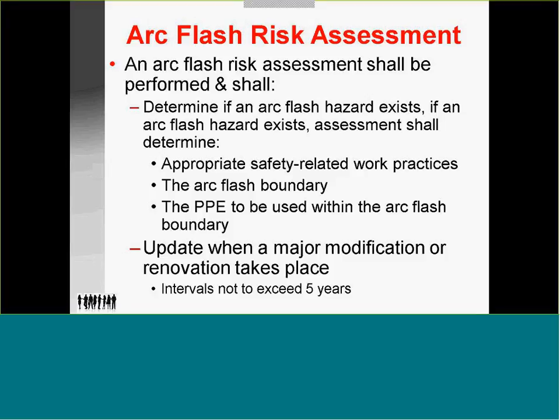Appropriate safety-related work practices, shielding, barriers, anything to protect the employee. The flash boundary. I'm working with a company right now where the arc flash energy would be 38,000 calories, and they have protection to 40, and the arc flash boundary was 9,160 inches. That would be quite a bit of a problem, and it was caused by not following installation requirements. The PPE to be used within the arc flash boundary will be category 1 through 4.